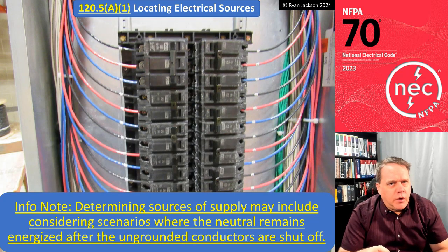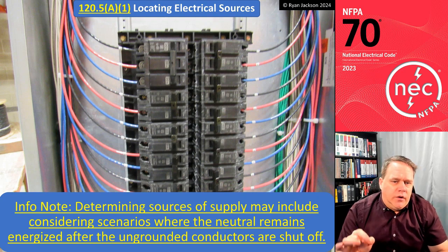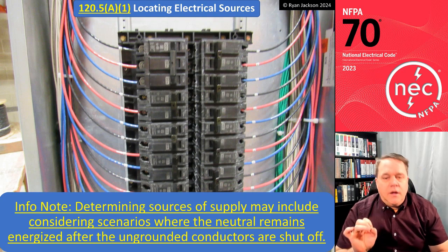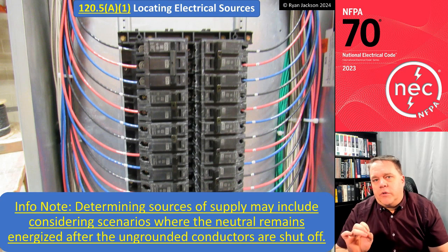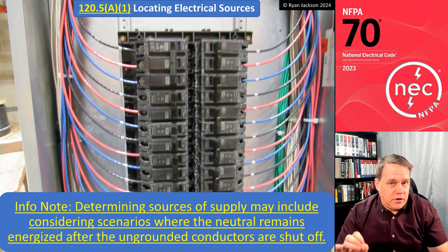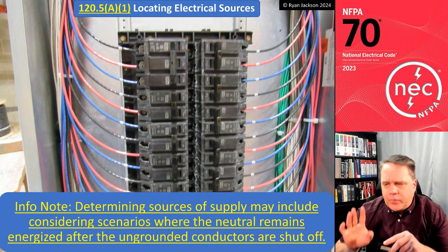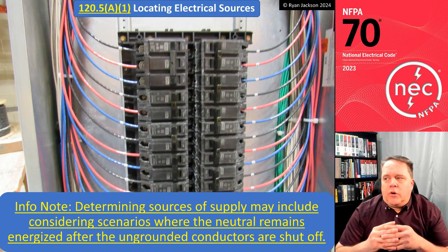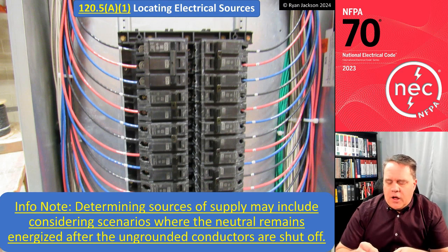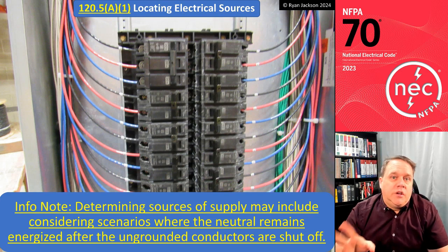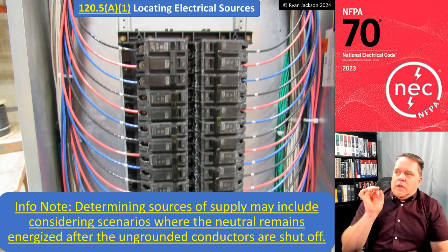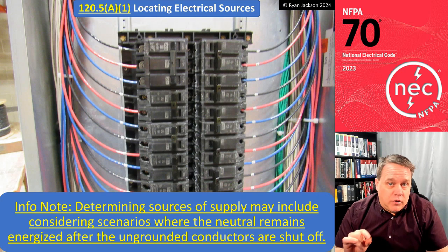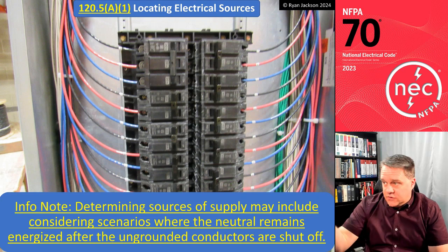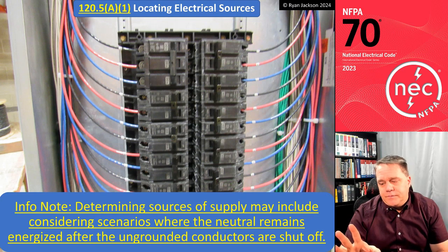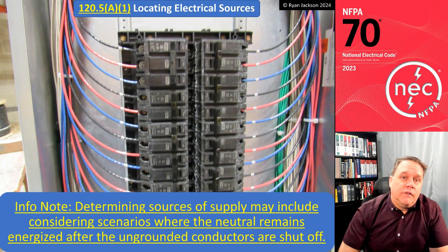What changed here in the 2024 edition is they added an informational note. It says, look, determining the sources of supply may include scenarios where the neutral remains energized after the ungrounded conductors are shut off. All right, so here in the picture, I'm showing a panel board, and although it's difficult to see, they're sharing neutrals in this panel board. So we're using multi-wire branch circuits. If it's installed after the 2008 code was adopted, then the disconnecting means, the circuit breakers, should have a 2-pole or a 3-pole breaker, or at least a handle tie to tie all of the shared phases together.